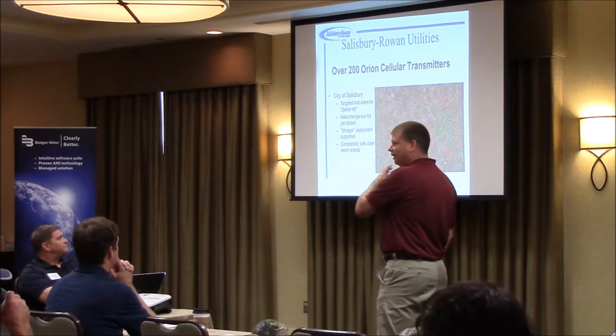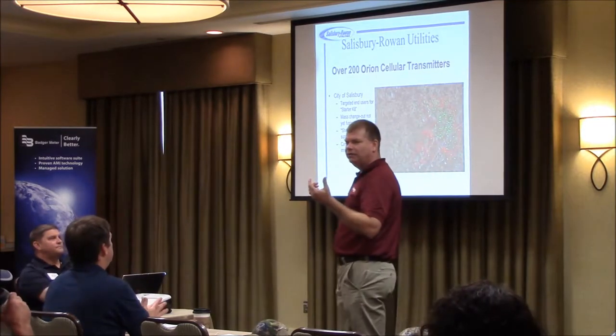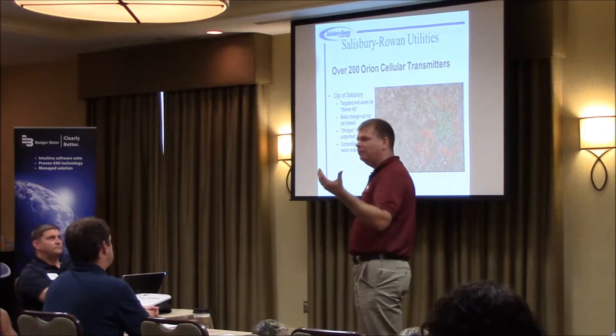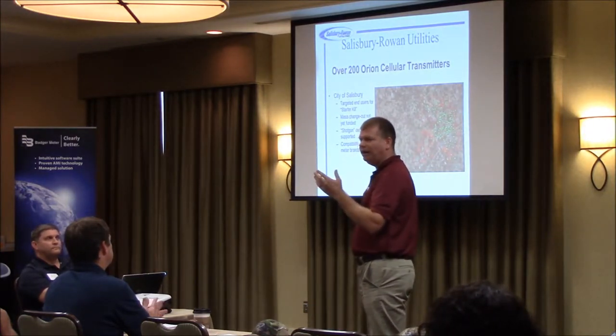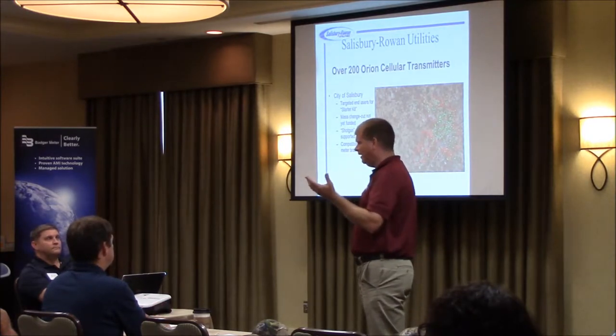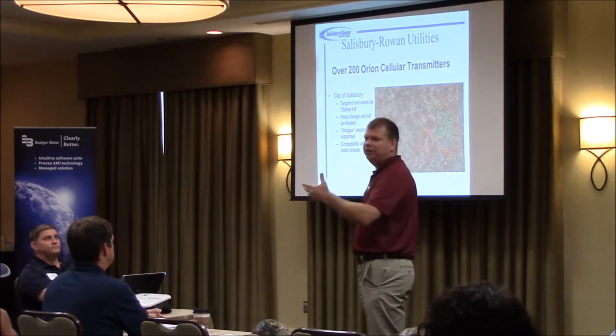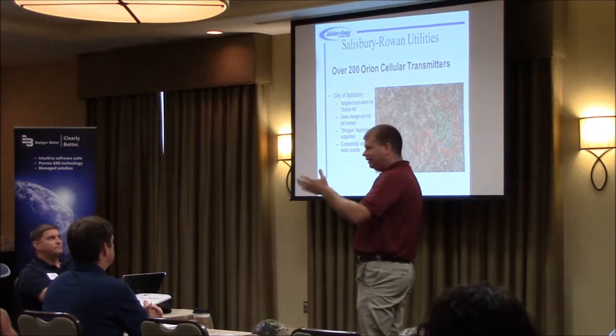So talking with the school system, they've got a guy on their side who really monitors their water usage. We put the one on at the elementary school, and right away we knew they had a leak. He knew he had more usage there per student than at all his other schools, but he didn't know why. As soon as we did that, we notified him he had a 30-gallon-an-hour leak, I believe it was. We actually went out there and helped him find a leak under a slab in one of the oldest parts of the school. They got that corrected, and we saw that.